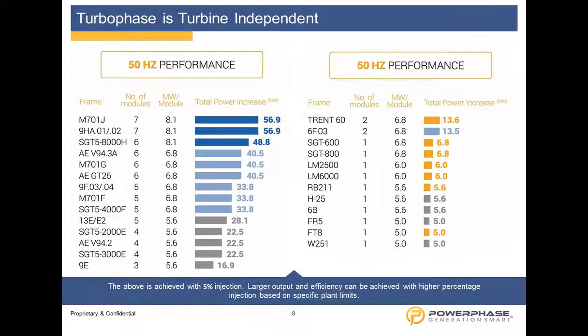I added these slides in here mainly for you all afterwards to review, but what I want to show here is 50 or 60 hertz. It's the same blue Turbophase module. Nothing changes about the module. We make a certain amount of kilograms per second, pounds per second of air production at a certain pressure and temperature. And when we apply those to different gas turbines, we are targeting 5% mass injection.